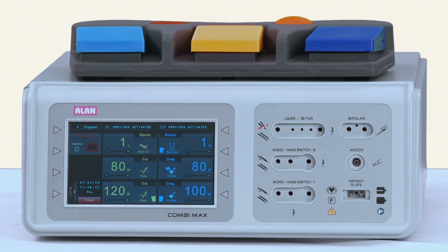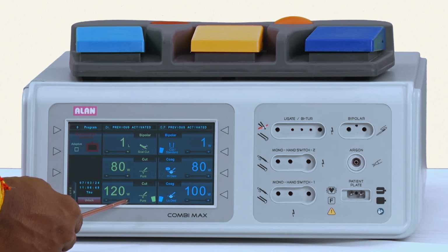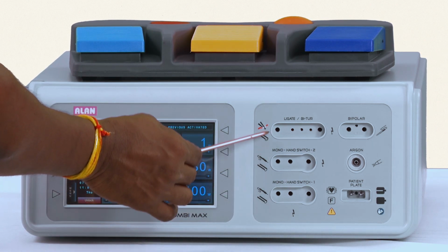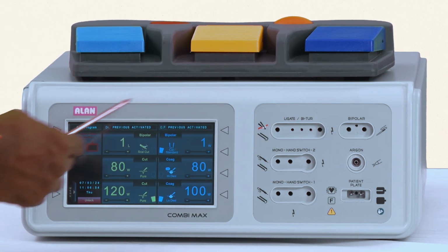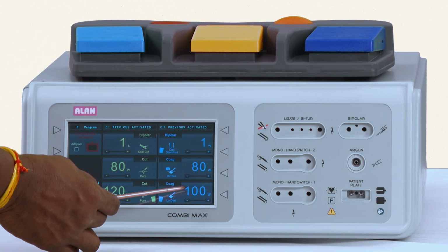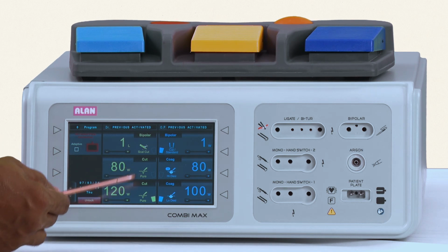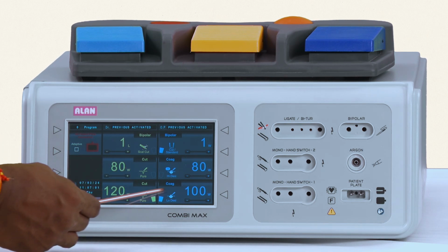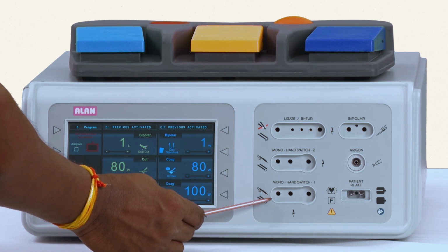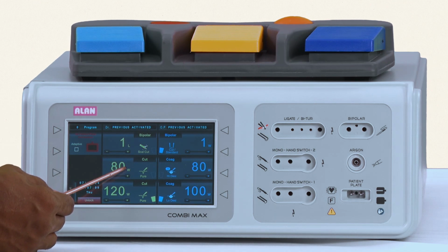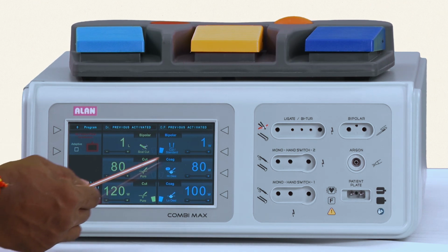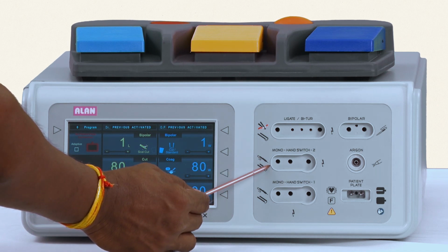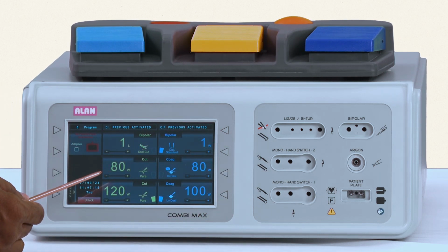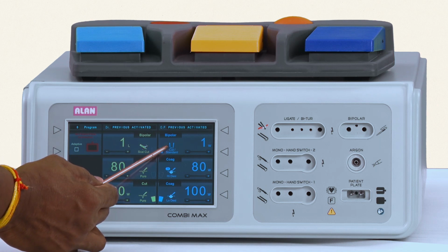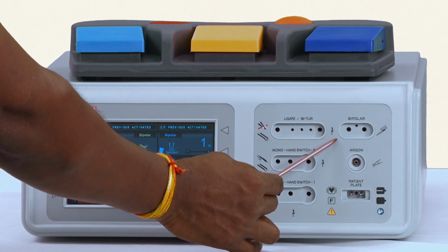In this segment, we will look into different types of modes, wattage changes, and instrument connection. The screen is divided into 2 columns and 3 rows. Now, whatever changes you make here in monopolar cut and monopolar coagulation, the output would come from this receptacle, mono hand switch 1. And whatever changes you make here in monopolar cut and monopolar coagulation, the output would come from here. Similarly, for bipolar, bipolar cut and bipolar coagulation output would come from here.